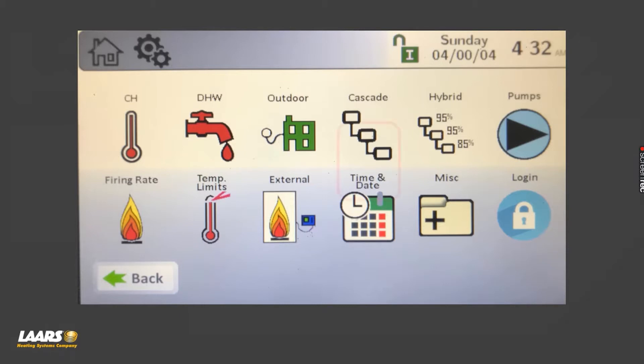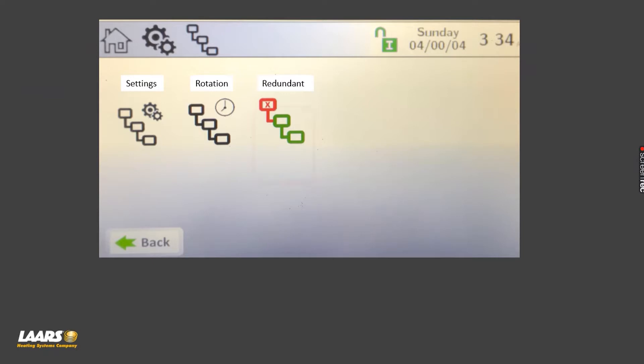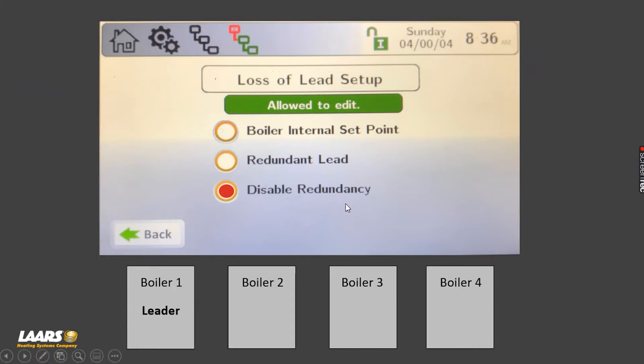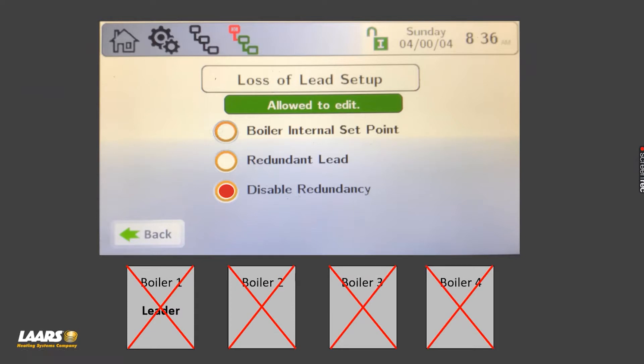From the configuration menu, choose cascade. Here you have some options. The first option I'll talk about is redundancy, and there are three options. The first is disable redundancy — at the bottom of the screen I'm showing four boilers, one boiler is the leader and that lead boiler gets the system sensor and all the setpoints. However, with disable redundancy, if someone has to power off that lead boiler due to maintenance or service, there's nothing telling the remaining boilers to come on and operate.